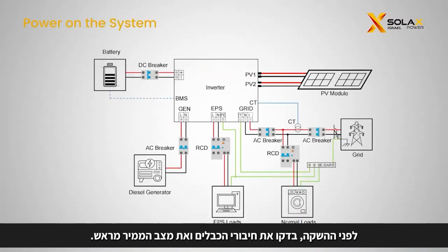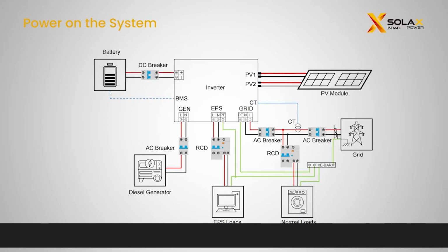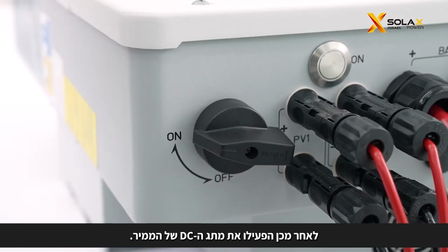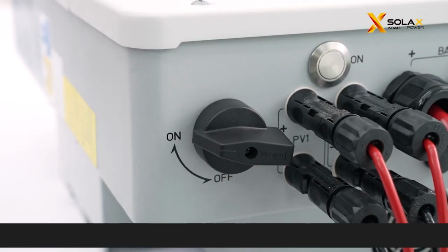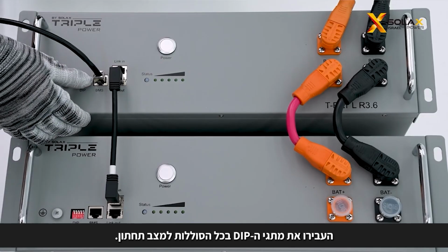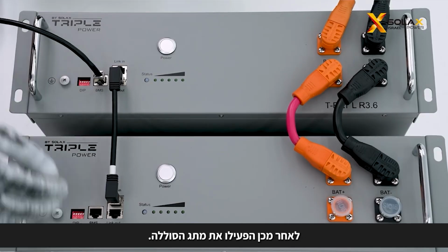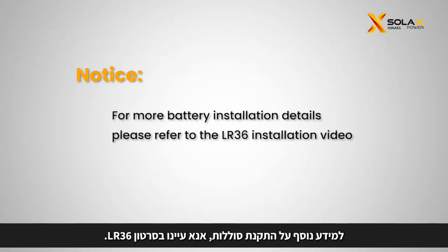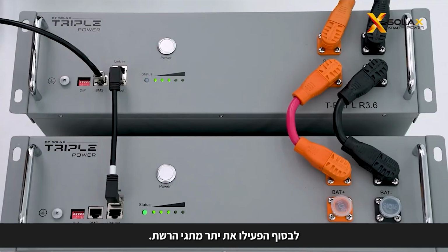Before commissioning, please check the cable connections and inverter status in advance. After that, turn on DC switch of the inverter. Turn the dip switch on all the batteries to the lower position. Then turn on the battery switch. For more battery installation details, please refer to the LR36 installation video. Finally, turn on other switches of grid.